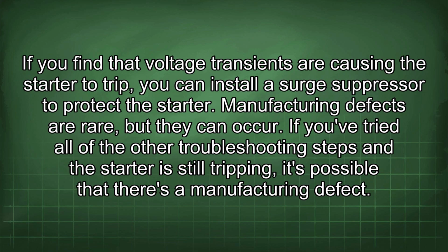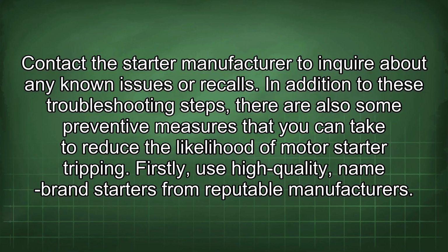If you find that voltage transients are causing the starter to trip, you can install a surge suppressor to protect the starter. Manufacturing defects are rare, but they can occur. If you've tried all of the other troubleshooting steps and the starter is still tripping, it's possible that there's a manufacturing defect. Contact the starter manufacturer to inquire about any known issues or recalls.